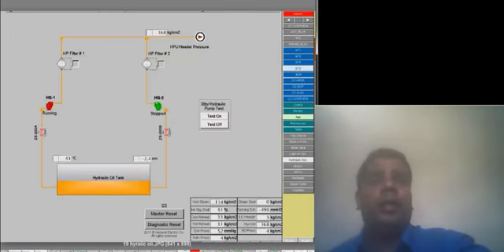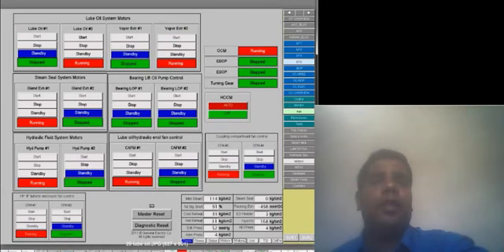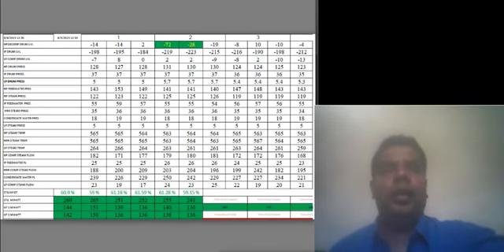And during pre-commissioning, we used to check all the materials available and drawings available, and that things were installed according to them. And in the commissioning stage, we used to follow up the cold and hot loop checks, RFI checks, and the startup process.